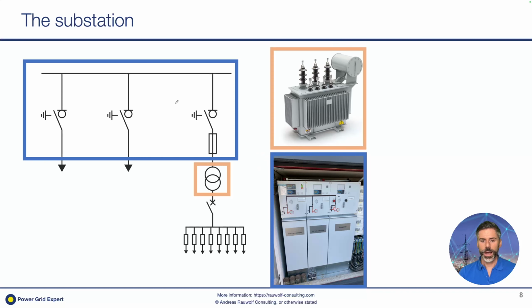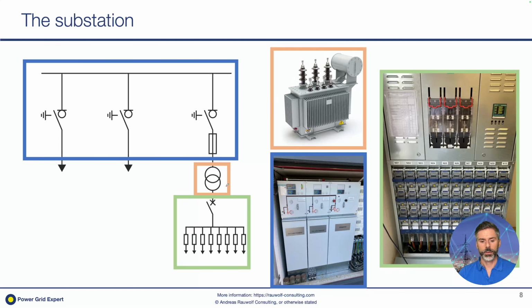Let's continue. After the medium voltage switchgear, we have the transformer that transforms the medium voltage down to low voltage, and we have the low voltage compartment and the low voltage distribution panel with the single feeders normally fused. Basically that's it. This is how secondary substations worked the last decades.